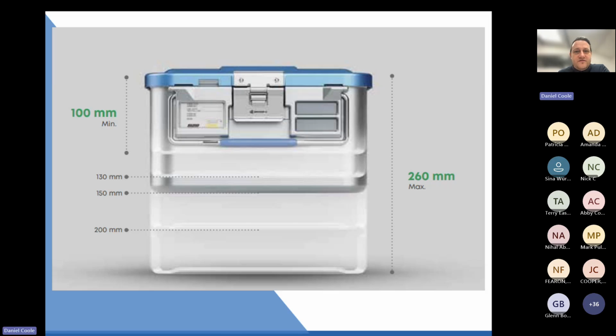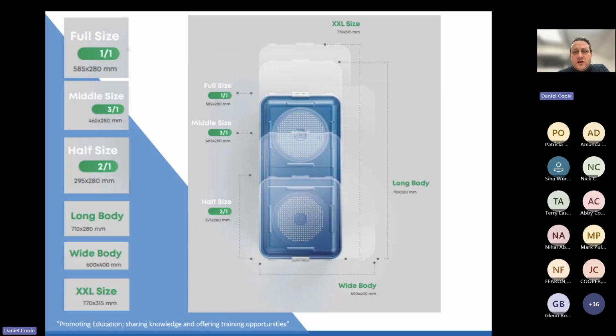Height wise, they come in a variety of different heights depending on the set and what's going in them. More commonly, we see sizes of probably 150 millimeters and 200 millimeters. There are also different widths. Here you can see the full size, which is 585 by 280 mil. That is pretty much the most common, which would fit around a standard DIN basket, the most common DIN baskets. There are other sizes as well, half size for smaller baskets and smaller sets. And there are some longer designs now as well, and these are generally to accommodate things like Da Vinci robot arms.